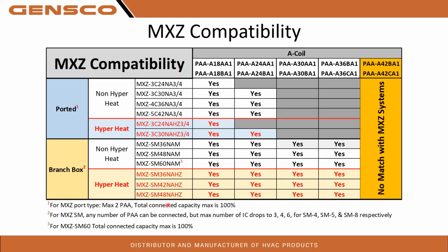Yeah, back to this here. Any number of PAA coils can be hooked up with the branch box systems. Just bear in mind that when you do that, your maximum allowable of indoor units drops down from 4, 5, and 8 for SM4, SM5, or SM8 respectively. So if you have an SM4, your maximum connected indoor equipment drops to a 3. If you're on SM5, drops to a 4, and if you're on an SM8, your maximum indoor units drops to 6. So keep that in mind. And also, if you're working on an SM60, your maximum capacity is going to be restricted to 100%. Again, can't oversize for those. And also, again, no matchup on the 42s.